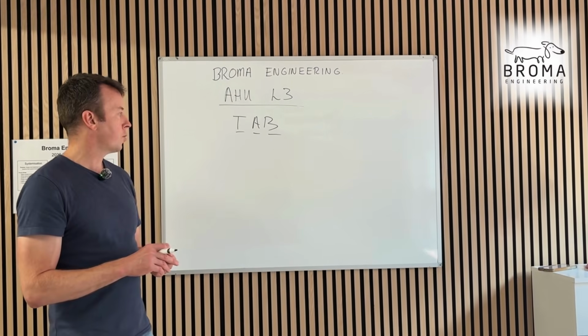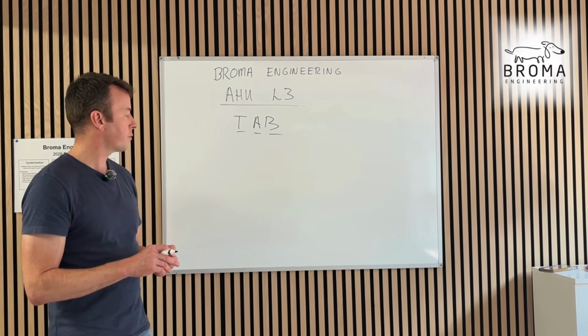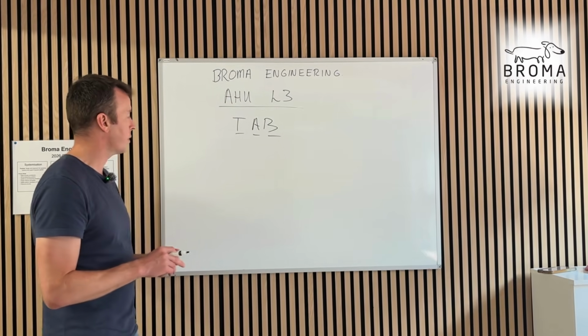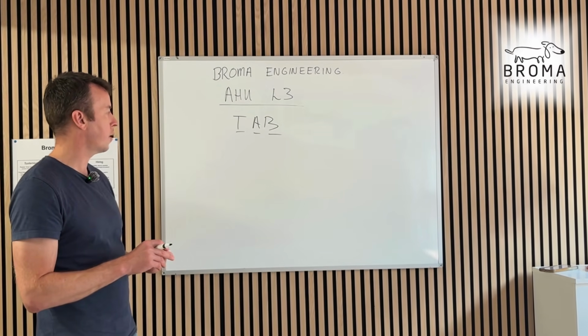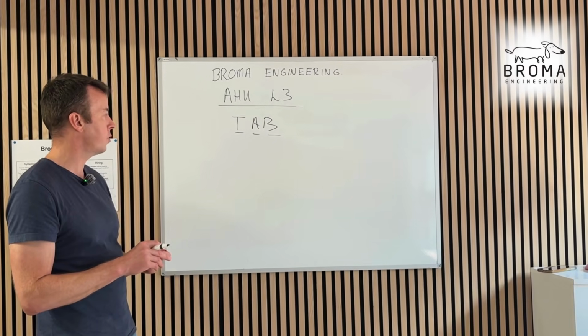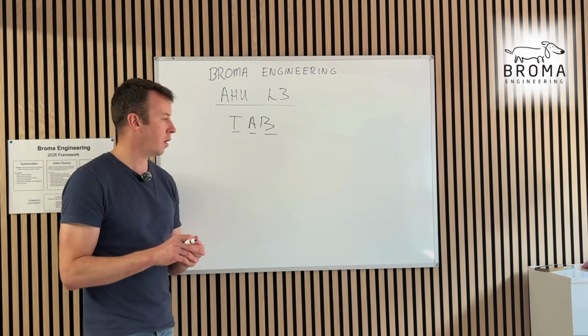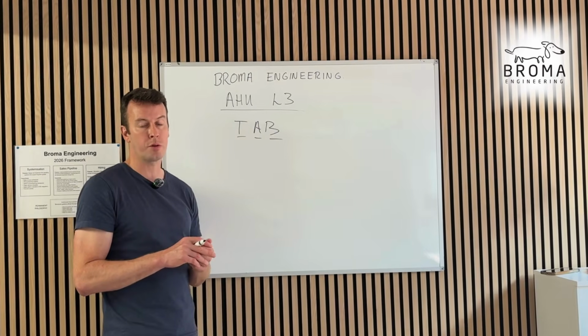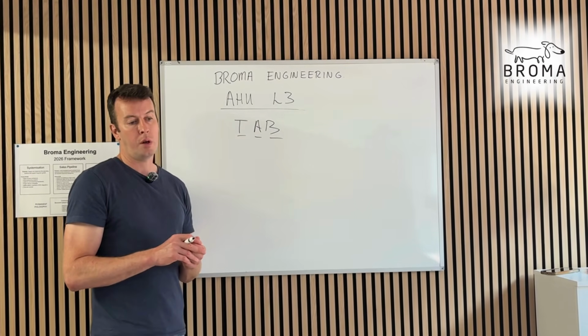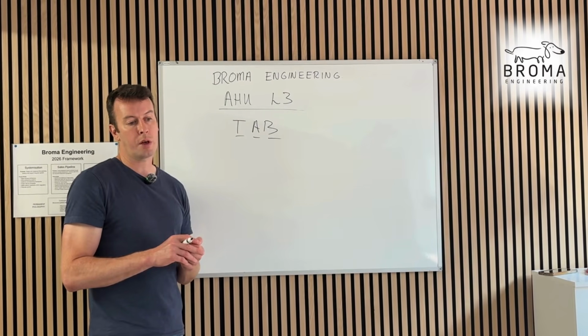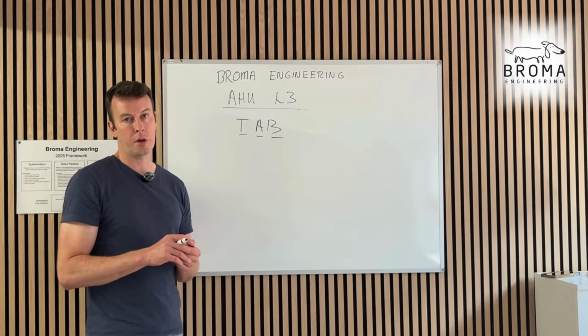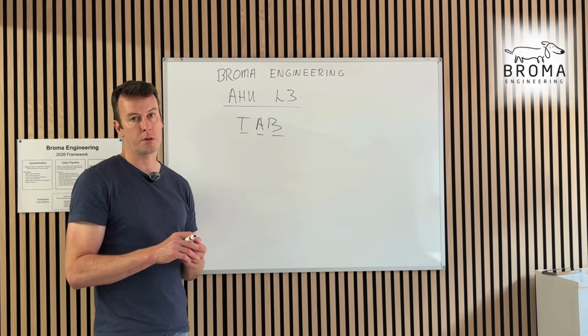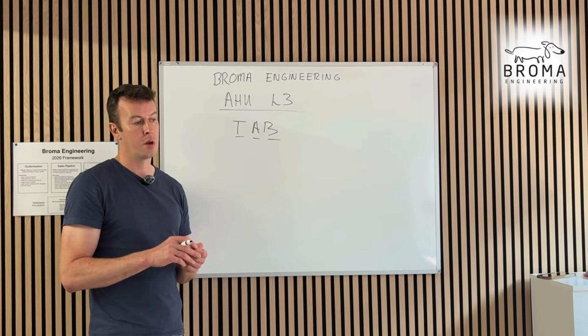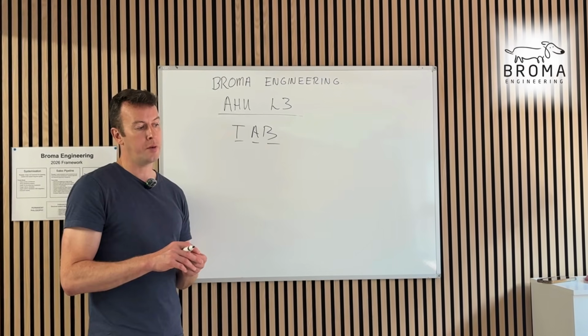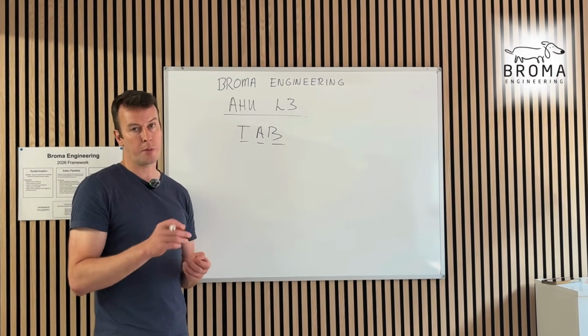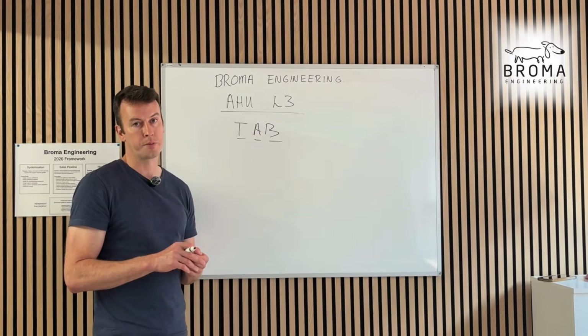We have to do all this adjustment. So what is TAB? We're getting our airflows correct, our water flows correct - adjusting dampers, valves, pumps, fans - making sure they're not under-pressured or over-pressured, creating airflows and water flows that are to spec, as designed. So we're verifying those flows are available and can be reached, then dialing them back if there's too much flow.